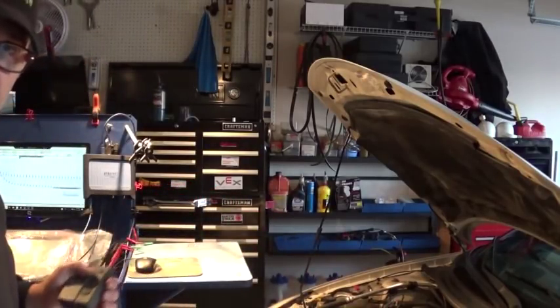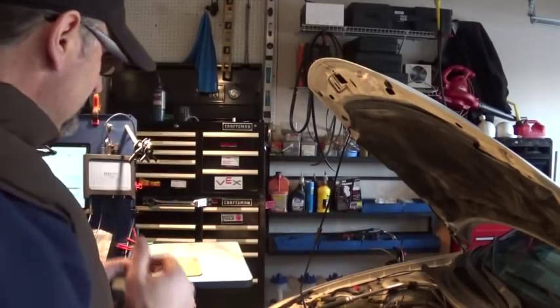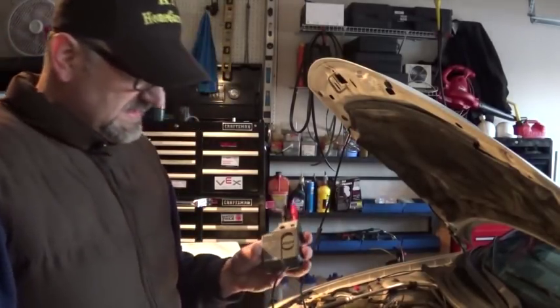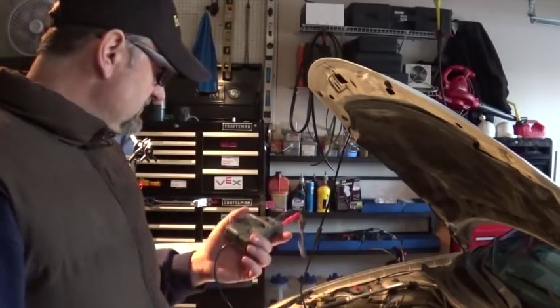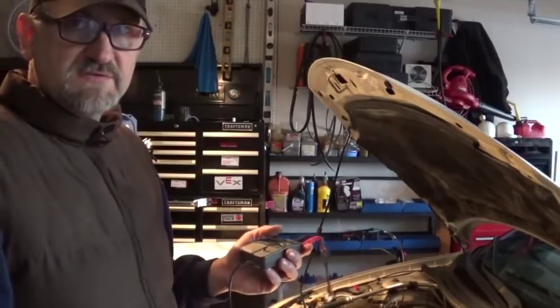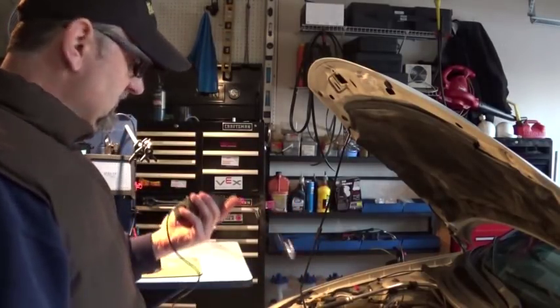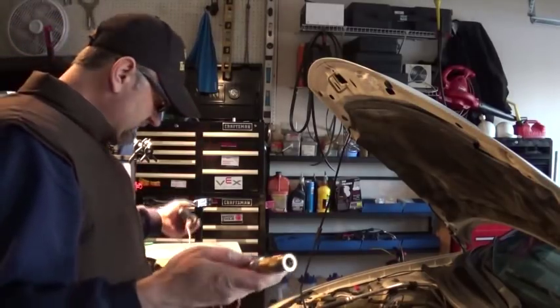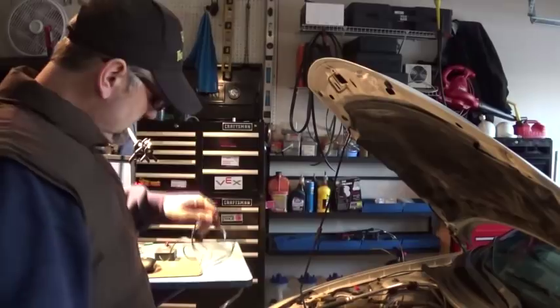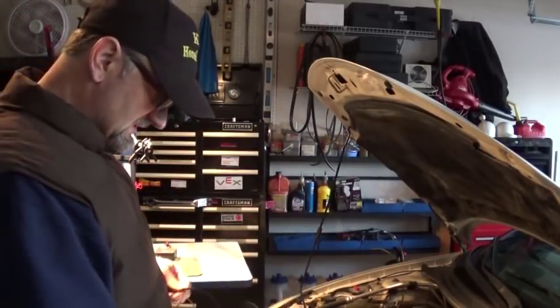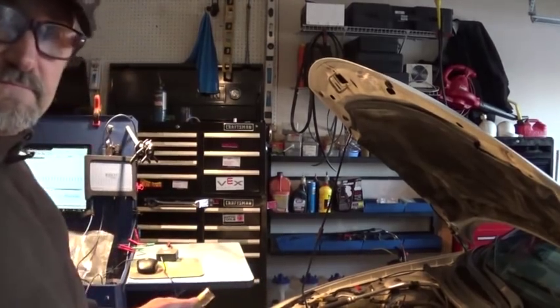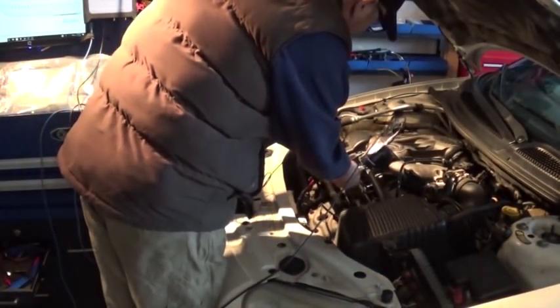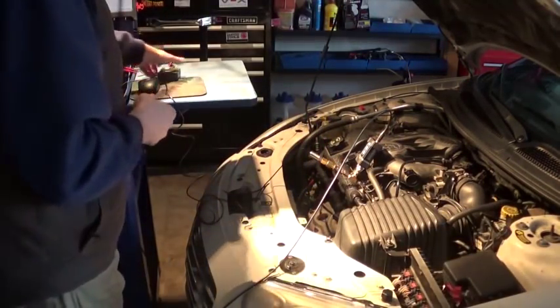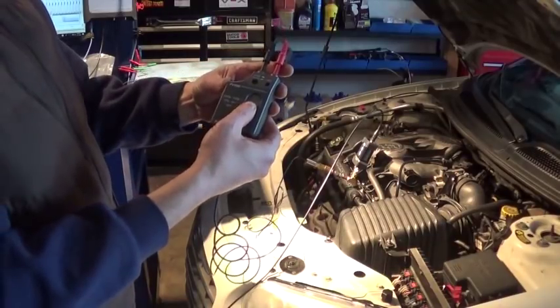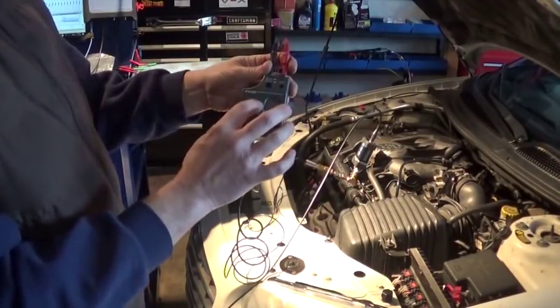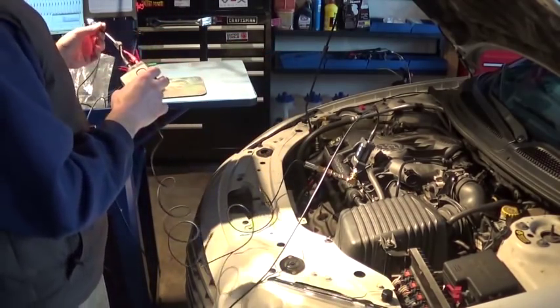So now I'm going to plug into my scope, and then we'll set the waveform. I did customize my probe for the FLUKE on my Pico. I'll show you guys, you just go to a custom probe and put times 1000, because that's going to give you 1 volt, and it'll work. Again, you don't have to, because simply 1 millivolt will be 1 psi or 1 kilopascal, whichever setting you choose to use. I'm going to connect the same cylinder, turn the unit on, leave it on PSI on English, plug into the scope, and see what we got.